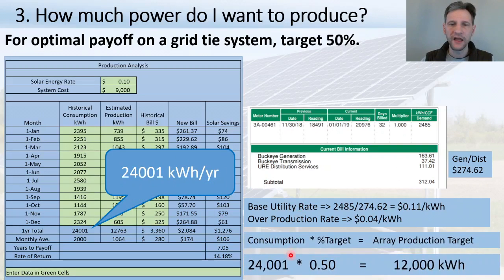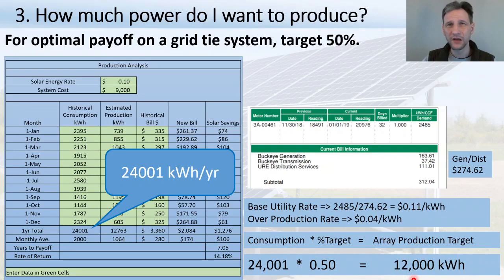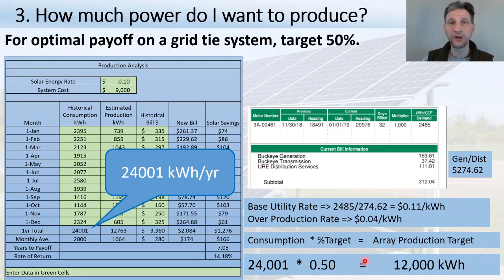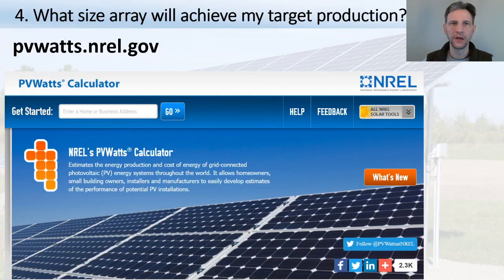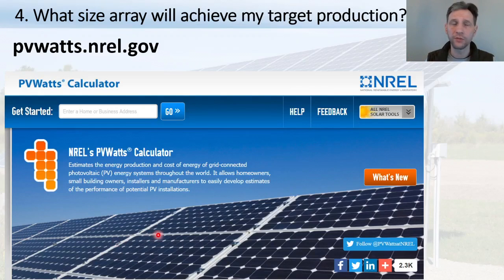So that's why I target about 50-60% as my production goal. Taking the 24,000 kilowatt-hour annual total and multiplying by 50%, the array production target becomes 12,000 kilowatt-hours. When I design my system I'm shooting for around 12,000 kWh, which keeps me under my consumption umbrella sufficiently to optimize my return on investment.